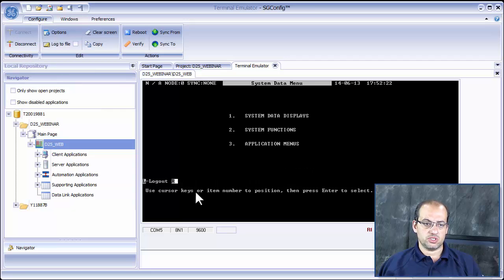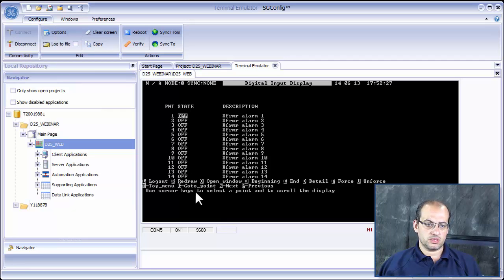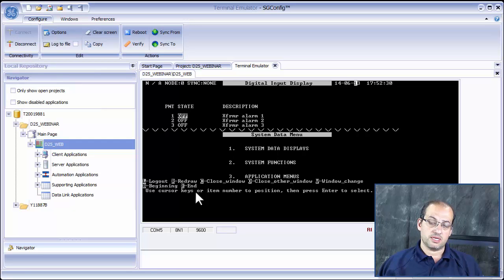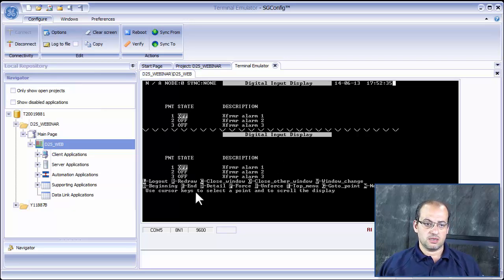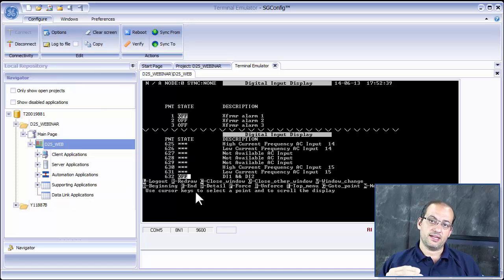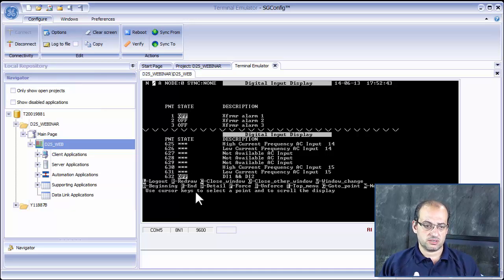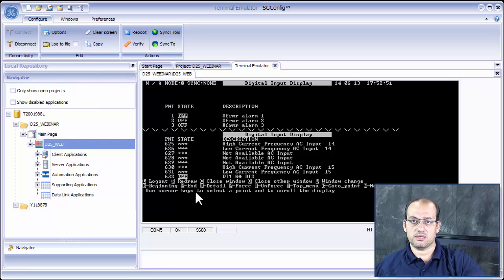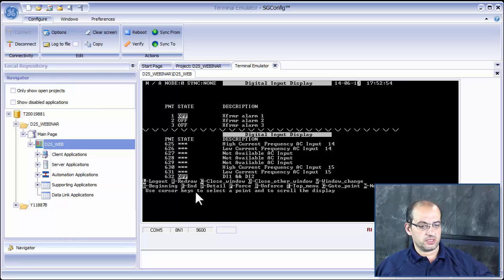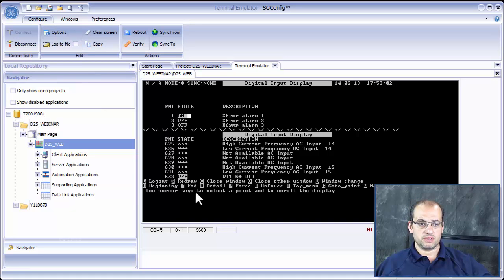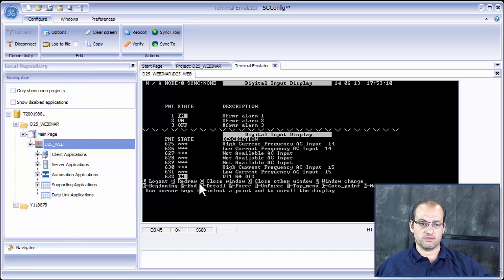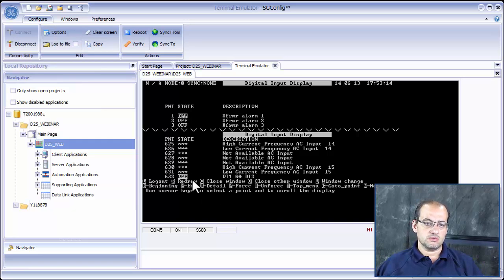I open the Digital Input Display in a second window. The Calculator point is point number 632, at the end of all defined points, while Plant IO has 631 points. Both inputs are off, so the AND output is off. If I switch the first one on — ON AND OFF gives OFF, which is normal. If I switch both on, the Calculator digital input becomes ON. If I switch one back off, it returns to OFF — correct AND logic behavior.